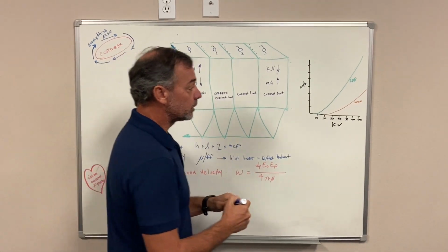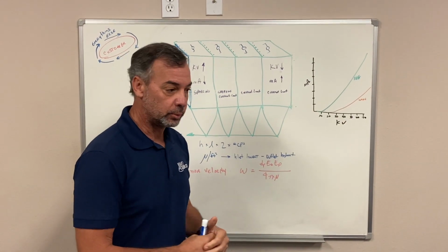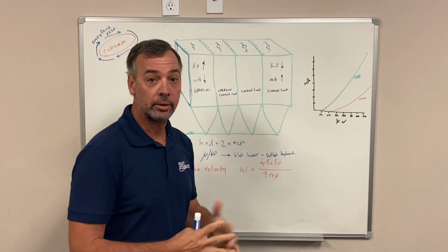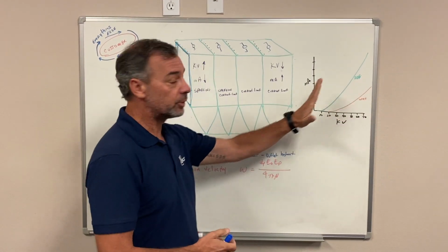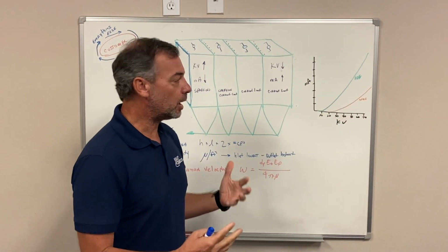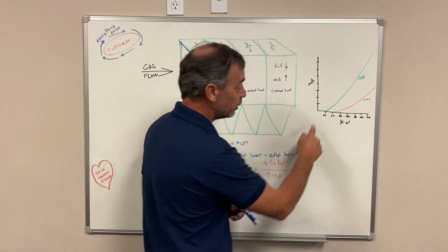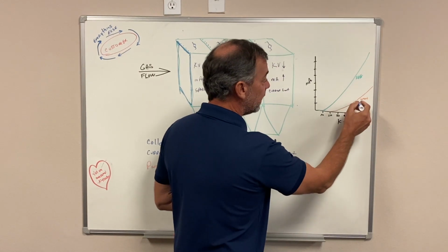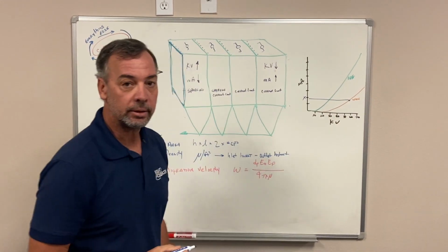What happens here is sometimes you will change your wires to a rigid discharge electrode, which stops the failures of these wires because RDEs are virtually indestructible. But you moved your VI curve. So if you didn't update your TR sets at that time, you may not have enough ampacity. So as you get up here to say 50, 60 kV, your current was X with the wires.